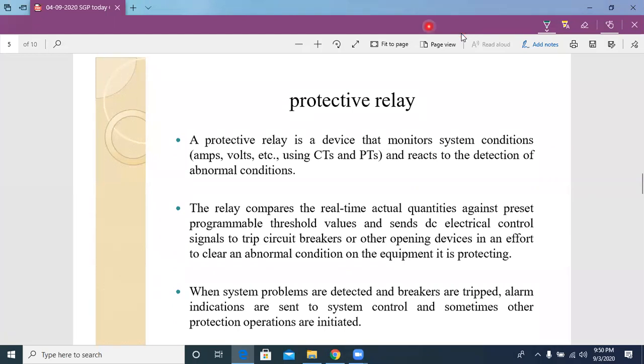So that same thing is explained in this slide. A protective relay is nothing but a device that monitors system conditions. Monitoring conditions, in the sense that it continuously monitors the system, either current, or voltage, or the phase angle between current and voltage, using current transformers and potential transformers.